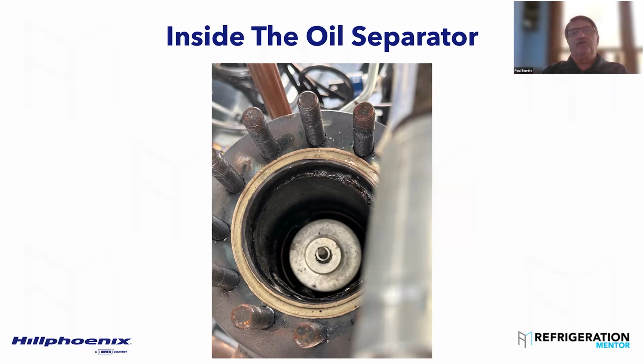Yeah, the one thing the control system brings to us is a centrally located diagnosis machine. You can see everything from there. You can see your case controllers. You can see your alarms out of your case controllers. You get your alarms out of your rack. You go into your alarms, you find out what you've got for an alarm, then you start there. You're not trying to guess what's going on. You have something that just told you, hey, look here first. If you went off on high pressure, but you got an alarm 20 minutes before that your vessel pressure was out of spec and too high, what are you going to look at?